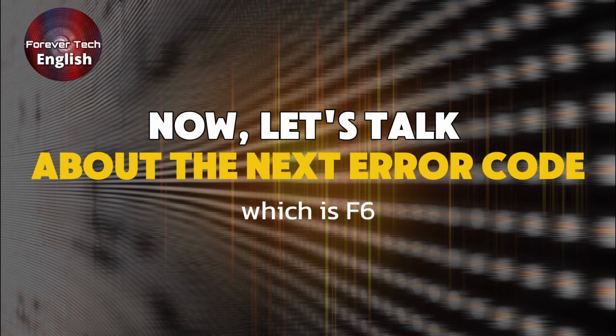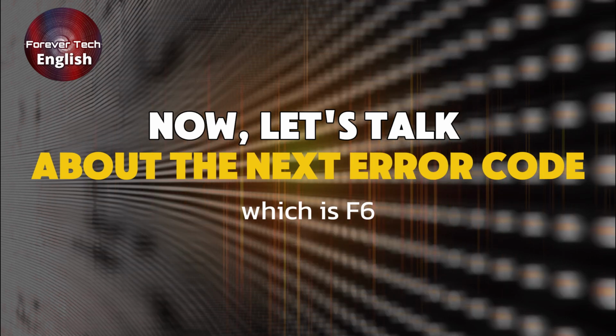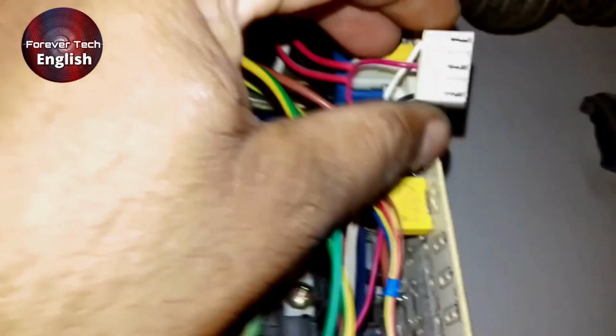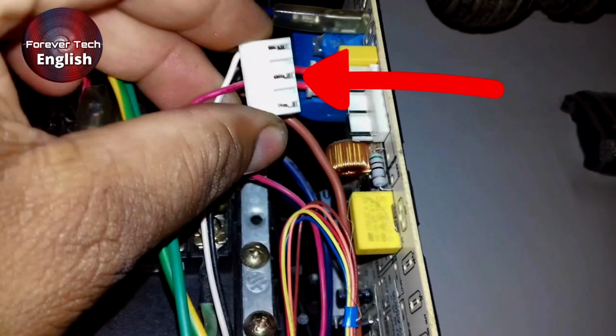Now I will talk about the next error code, which is F6. This error code indicates a motor feedback fault. It means that the motor is not providing feedback to the circuit. Here, you can see the connector through which the motor operates, and it is also installed on the PCB.